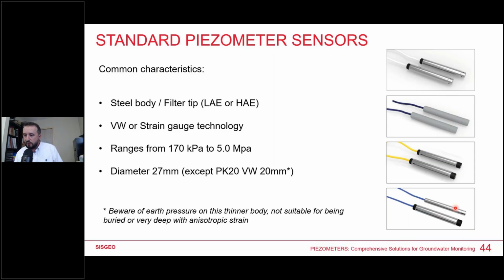So this one is very small here, the PK20. The PK20 is a very thin vibrating wire sensor that can enter into smaller piezometer tubes, for example, 20 millimeters in diameter. And just pay attention when you are using this sensor, because the body is made of steel which is thinner than the standard one. And because it's thin, it's not suitable for being buried or installed very, very deep when you have some anisotropic strain. In this case, we will not monitor only the water effect, but also the earth and the loading effect. This is why this sensor has to be used only in a protected environment and not too deep.